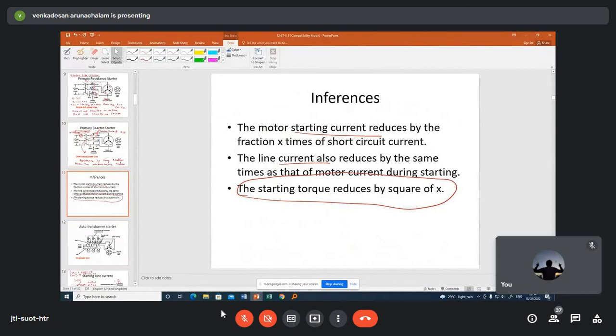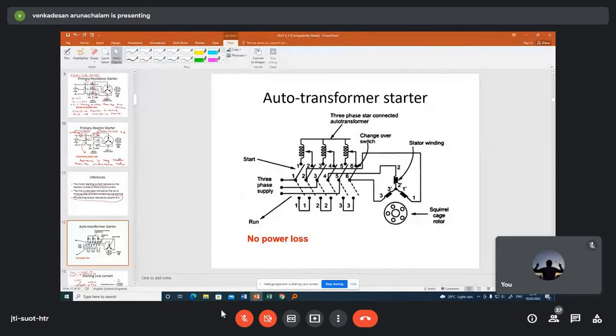So that starter only, here it is shown with the switch. During starting condition, maximum reactance is added to the motor winding. This switch is a double throw switch, or in other words, it is called a changeover switch. So it is connected here. That is the starting position. You see here all the ends are connected together. The reactance ends are connected together. So that is the auto transformer starter.